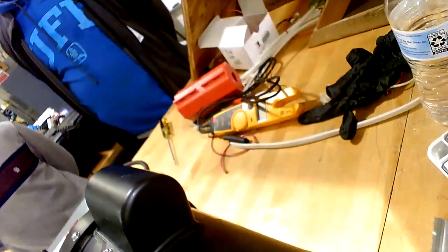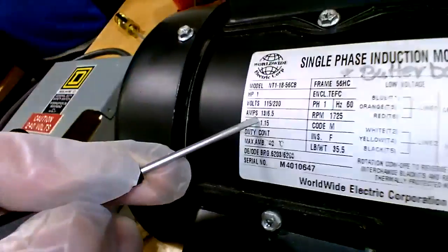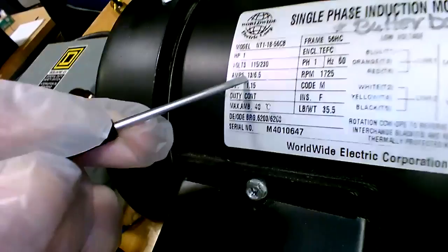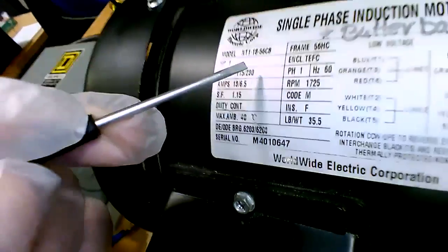And so if you wonder, is that okay or not? You close that up, cut that off. You go up to the nameplate. So the nameplate is telling you, see where it says amps. If you're running on 115 volt, the amps under full load would be 13 amps. If you're running 230 volt, the amps would be half of that, 6.5.